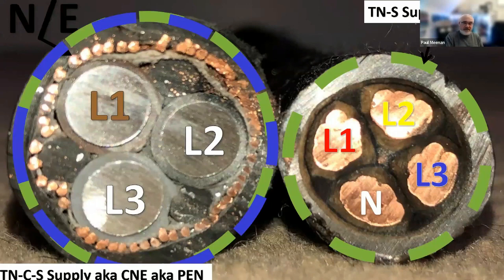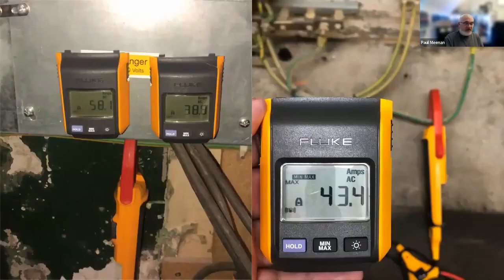So this is a challenge at the moment in the UK. It's a growing challenge. It's nothing that people need to panic about, but we just need to raise the profile so that people can check and ensure they're safe. Safe working is key. Here's some more images to show you how dangerous this can be. Just some clamp meters around earthing conductors, 43 amps, 58 amps. So it is very much real.